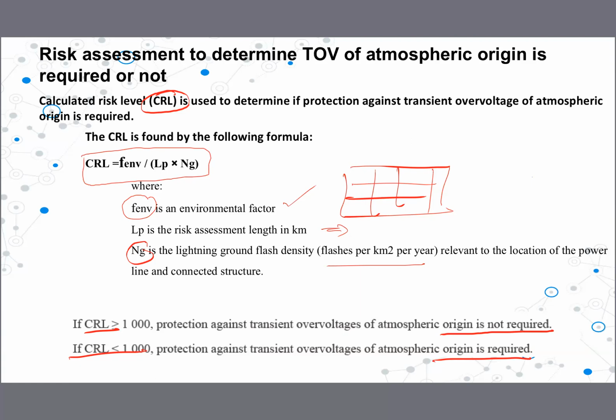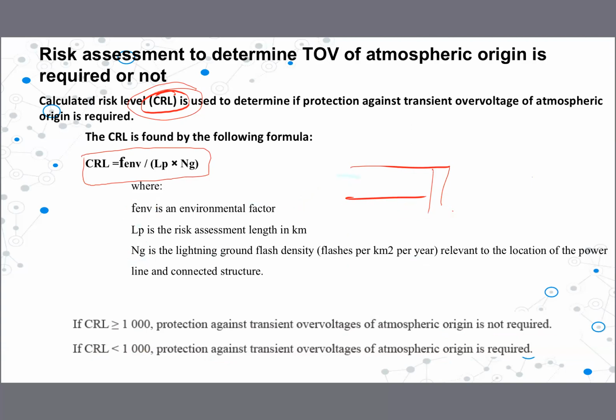Transient voltage of atmospheric origin, right? What we need to protect against. So we need to find this out, and we need to see the result, whether it's less than 1000 or more than 1000. Depending on that, we can decide, right? Actually, this is in the 17th edition as well. The 17th edition also says you do this and see whether you want this protection or not, right?